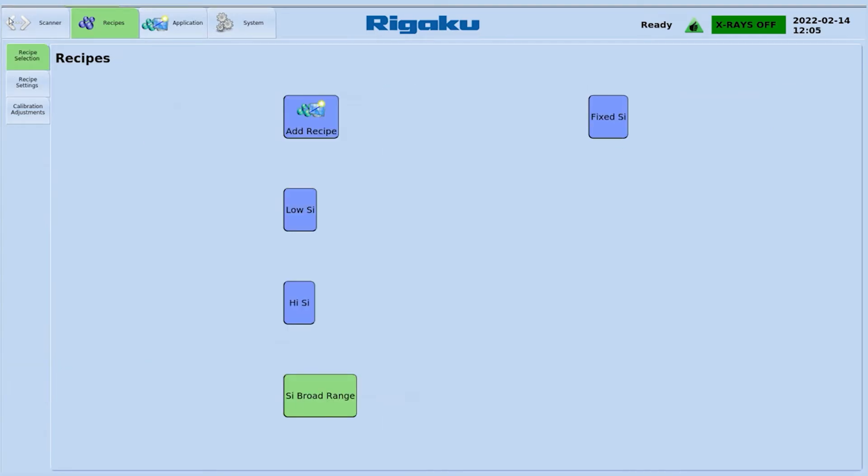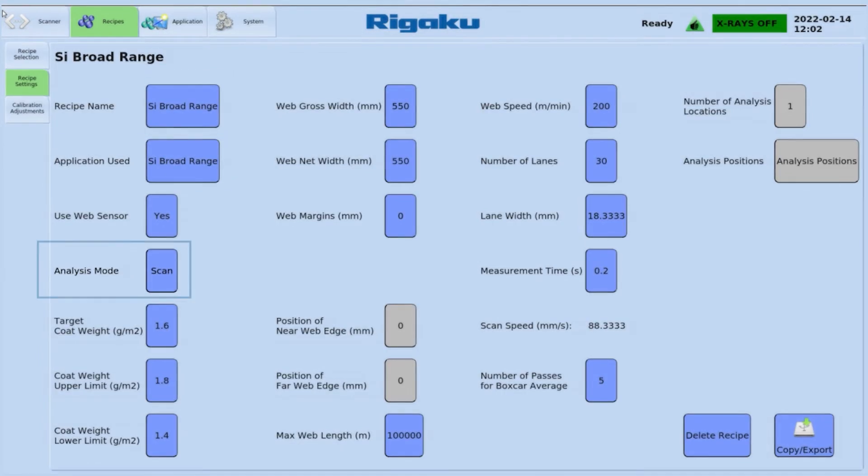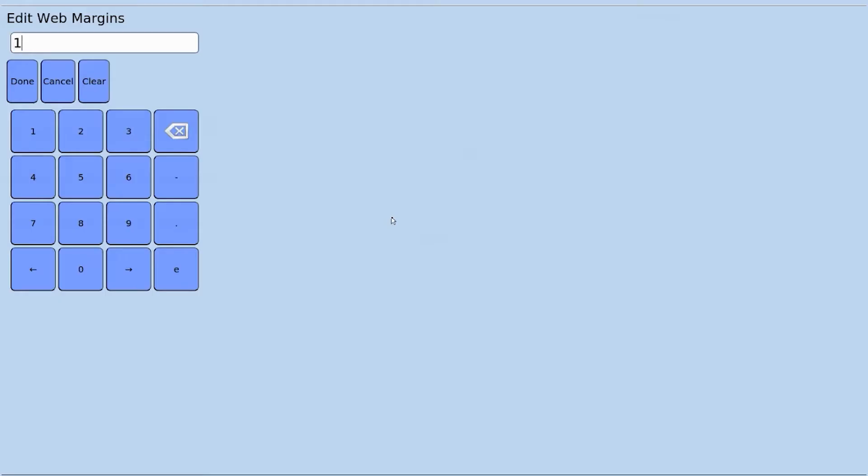To add a new recipe, simply name it, select the application, define your measurement mode, and enter your process parameters to allow for tighter control tolerances.